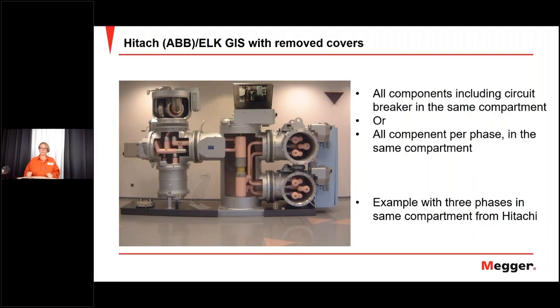And this specific one is an ABB, or as it's called now, Hitachi circuit breaker or switchgear, ELK. In this picture you can also see a little bit showing the mechanism. Up here you have a mechanism on this circuit breaker. They put a mirror here so we can peek a little bit into the circuit breaker.